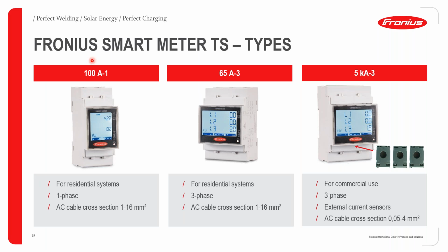Looking specifically at the new Fronius smart meter series, the touchscreen, we have 3 types. We have 100 amps single phase for residential use. We also have 65 amps 3-phase for residential use. The cable cross section that you can feed to either the 100 amp or 65 amp residential smart meters is up to 16 millimeter square. For commercial applications, we are talking about a 5 kilo amp smart meter in 3-phase with a maximum cable cross section of 4 millimeter square. The reason for this is that you do require external CTs for current measurement. For both the 100 amp and the 65 amp, as well as the older version of the smart meters, you can measure the consumed current directly, but for the commercial smart meter, you need external CTs to be able to handle that current safely.